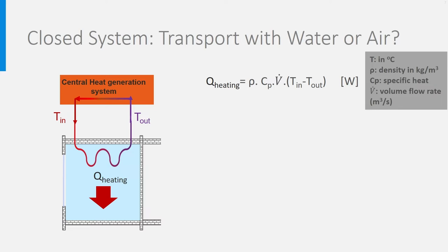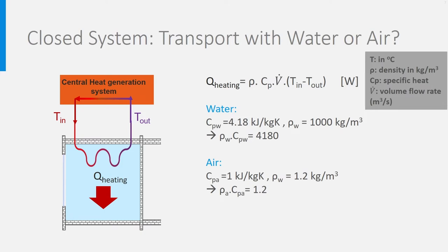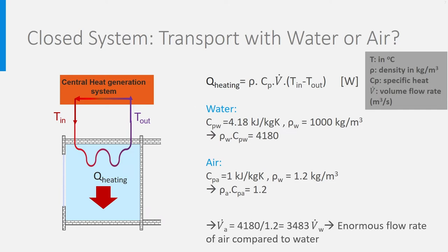Let's compare the properties of water and air. For water, the specific heat Cp is 4.18 kJ per kilogram Kelvin, and ρ is 1000 kg/m³, giving ρCp = 4180. For air, Cp is 1 kJ/(kg·K) and ρ is 1.2 kg/m³, giving ρCp = 1.2 — quite a difference from water. This difference must be compensated by a much higher flow rate of air compared to water if we want to transport the same quantity of heat. The volume flow rate of air must be 3,483 times that of water — what a difference!